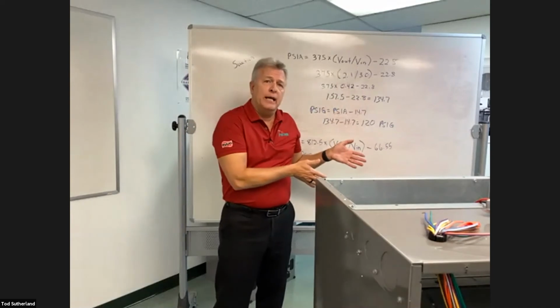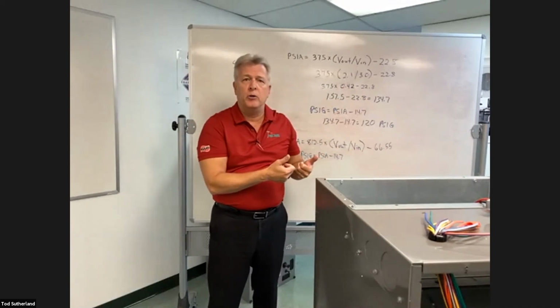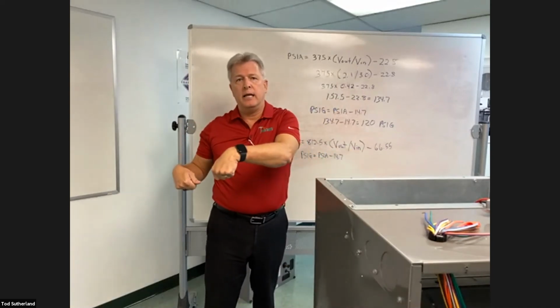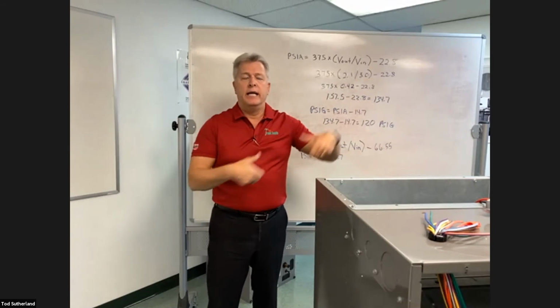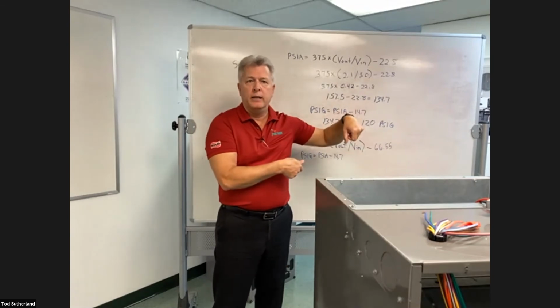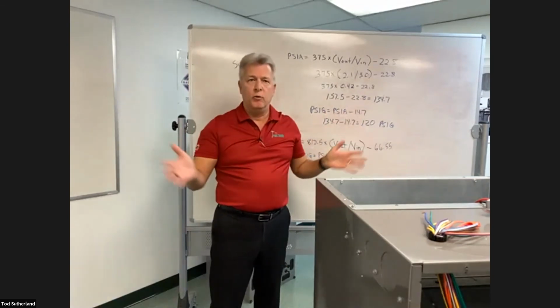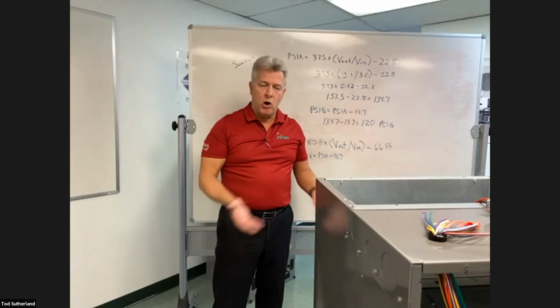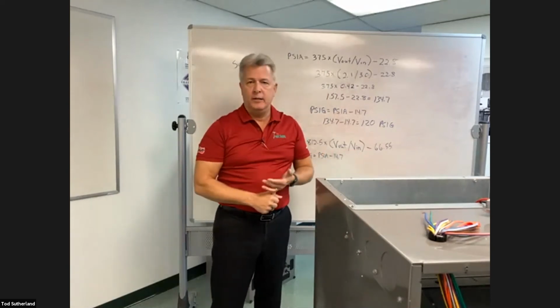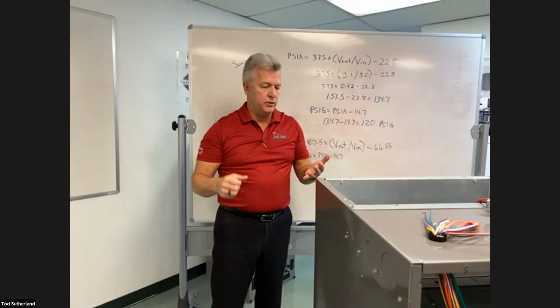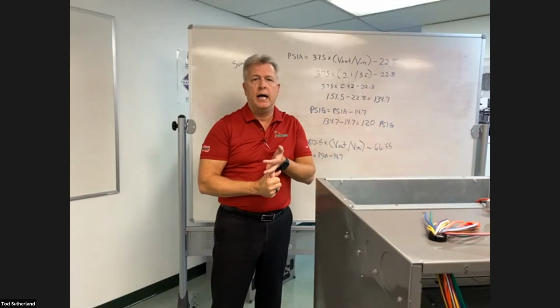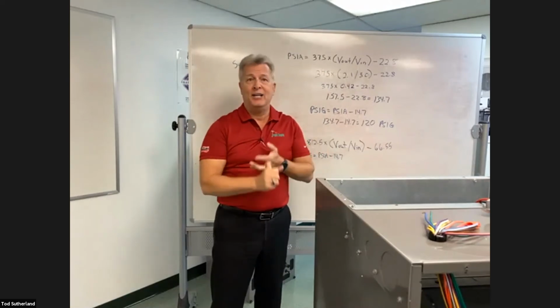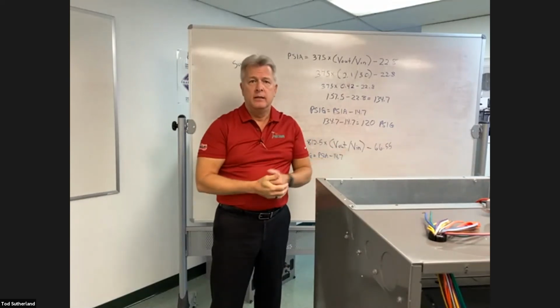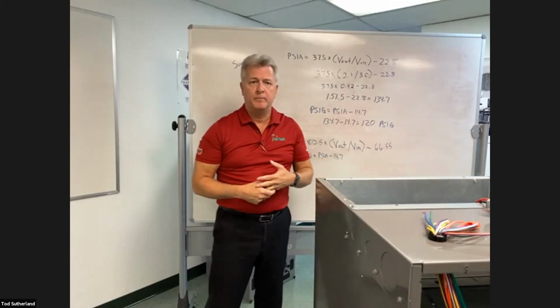The way you would account for that is you're going to take your temperature clamp on probes and you're going to check your line temperature at the outdoor unit, check your line temperatures at the indoor unit. That'll give you an idea of whether or not you have any of those issues. Water in the chase pipe, dent in your copper line that's reducing the pressure, line going through a hot attic that's picking up heat, maybe flashing gas before it even gets to the evaporator, so on and so forth.